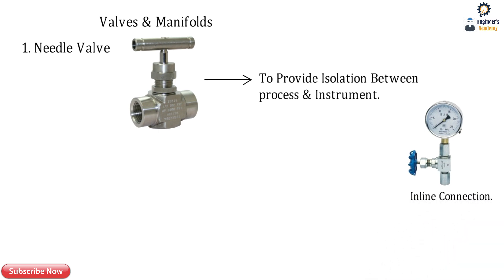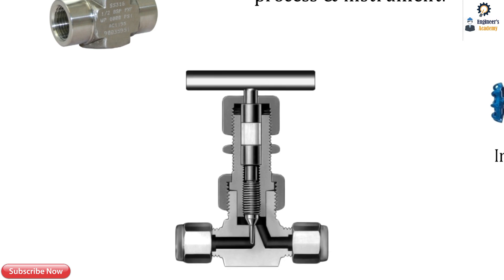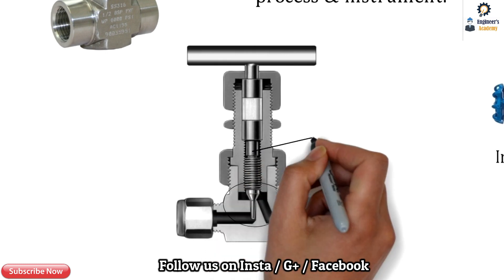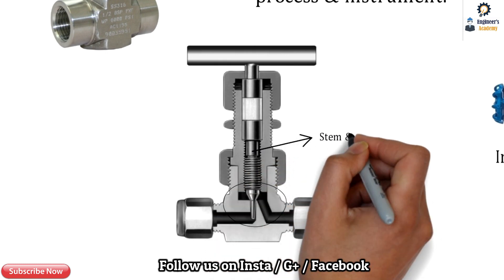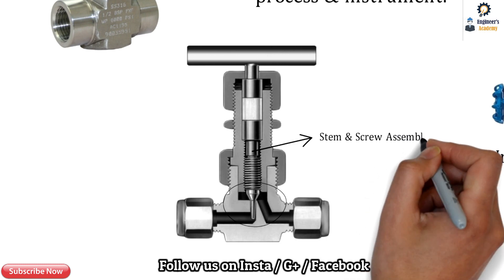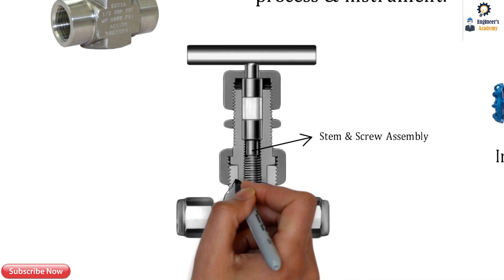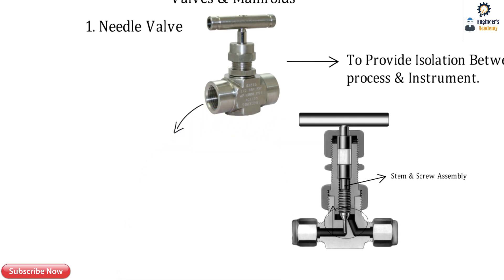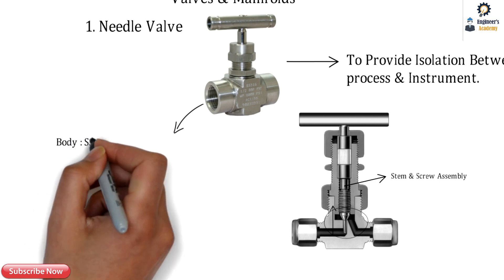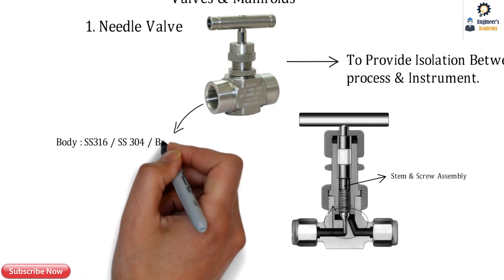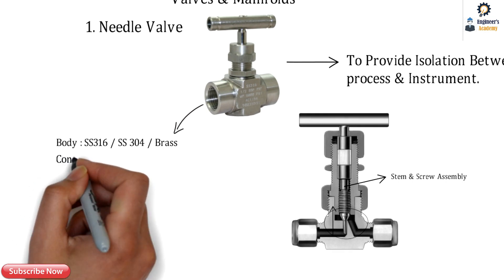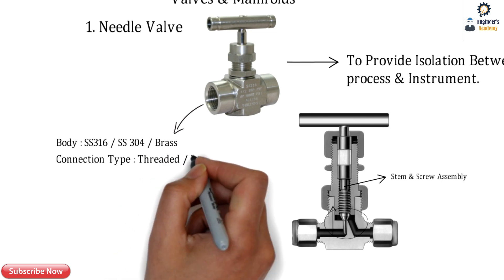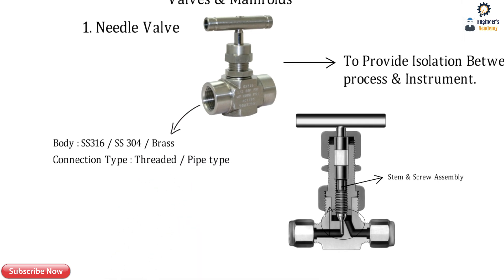This sectional view represents the needle valve. The needle is actuated up and down by a stem and screw assembly, which allows flow to pass from left to right. Regarding specifications, the first and most important element is the body. The body can be made of SS 316, SS 304, or brass, which is less costly.